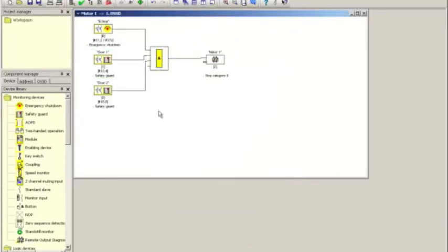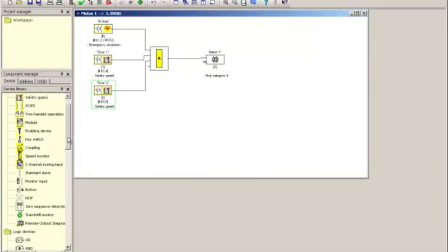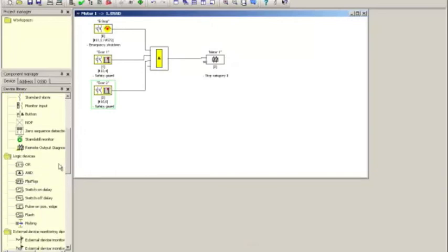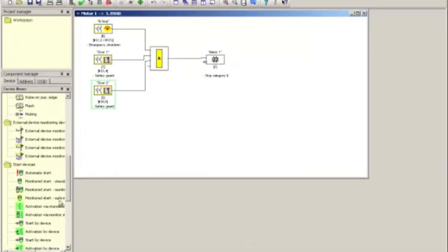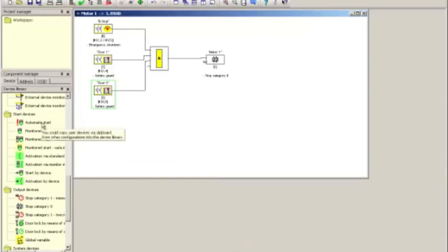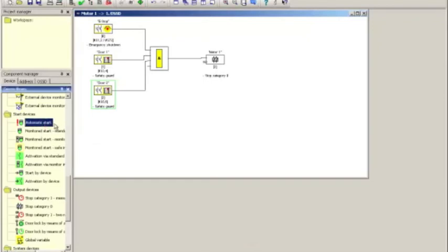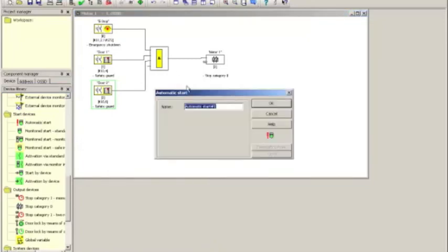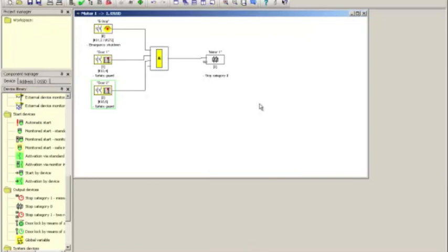Last thing that needs to be done is to add the restart function. And because I have put the reset directly into the e-stop function block and I want the door switch to auto-start, I will utilize an automatic start as the overall startup condition and drag it here. I don't have to change the name. I can if I want to. I just simply click OK.